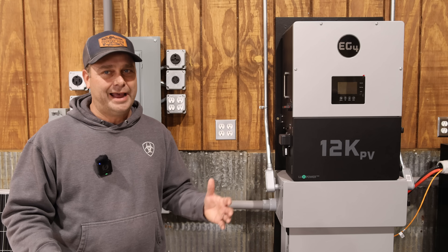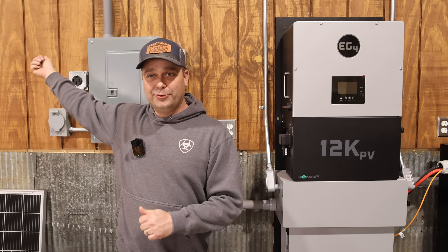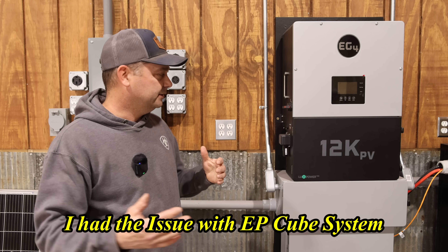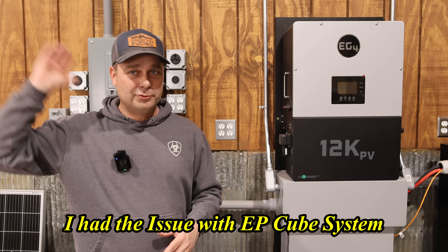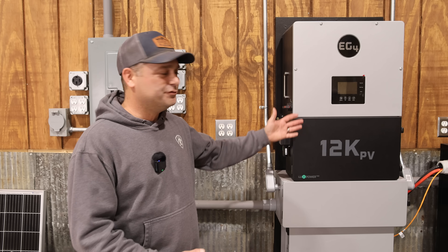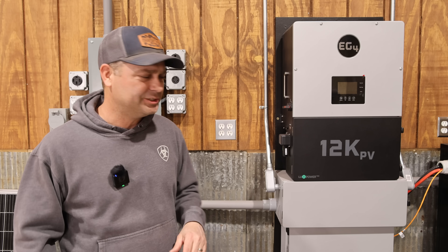For a total of those last seven days being 44 kilowatt hours that I purchased from the power company. So the readings don't quite match. The reason they don't match is because my CT sensors are all the way up there — I've got a long piece of cable and it could be subject to noise and induction from other electrical wires in the ceiling, and that could throw off the reading. I want the EG4 and the power company readings to be as close as possible to matching.